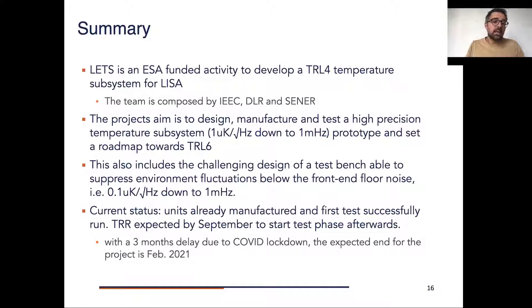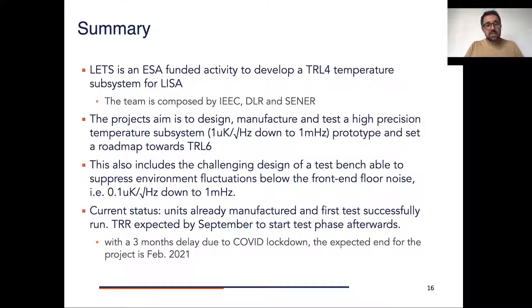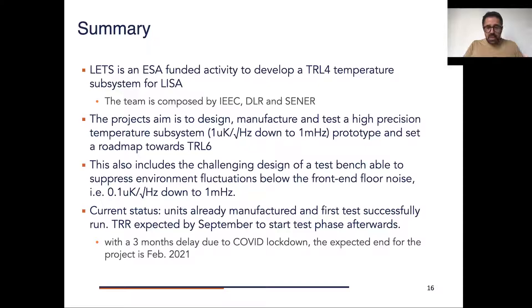To conclude, I will give you a brief summary. LETS is an ESA-funded activity to develop a TRL 4 temperature measurement subsystem for LISA. The team is composed by people at IEEC Barcelona, DLR Bremen, and Sener. The main goal is to design, manufacture, and test a high-precision temperature subsystem reaching one micro Kelvin, and to set a roadmap towards TRL 6. This also includes the very challenging activity of designing a test bench able to suppress environmental fluctuations below the front-end floor noise. The units are already manufactured, a first test has been run successfully, and we expect to hold the test readiness review in September and then start our testing phase to finish around January–February next year.